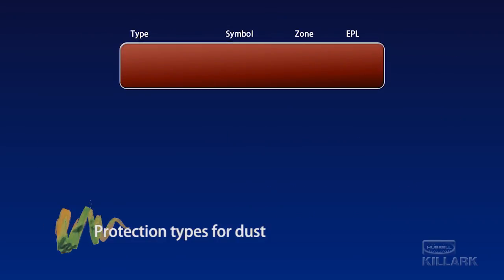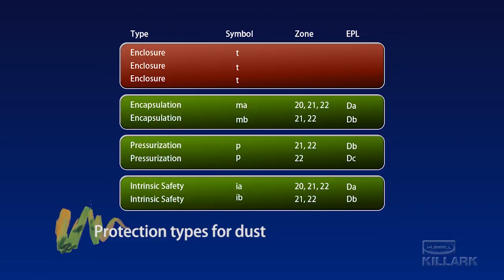The all-important dust protection by enclosure, Type T, is added to the table, along with the other now familiar protection techniques. Type T dust protection also has the added EPL of A, B, or C to designate whether the equipment is intended for Zone 20, 21, or 22. One additional but intuitive difference that is also quickly apparent in the table is that the designation G, used with the EPLs for application in the gas and vapor risk zones, has been replaced with the letter D for dust.